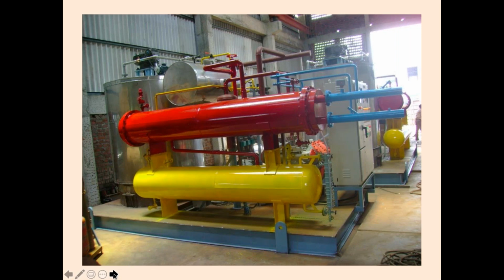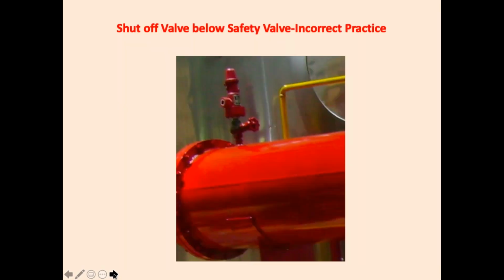Now look here, this machine looks very well painted, well maintained. But what is the biggest mistake they have done? They have provided a valve below a safety valve, which, as I have mentioned, is not recommended by the standard. But a lot of people say the Indian valves start leaking, therefore we need to provide a valve. I won't object to that. If you provide this type of valve, keep it fully open, remove the handle, and that handle should be in the plant manager's lockup so that nobody accidentally closes this valve.